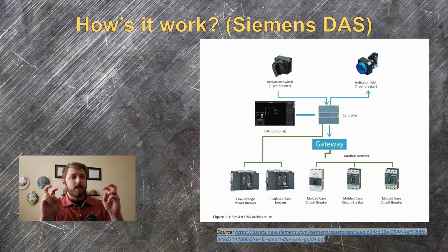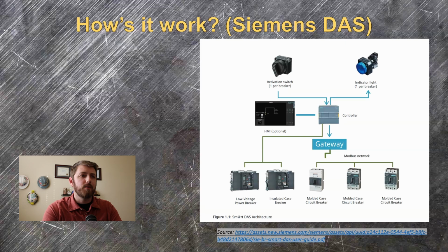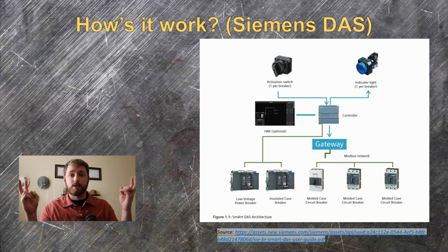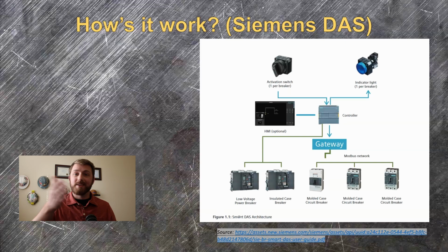Siemens Smart DAS system is similar to Square D's ERMS system. Implementation requires a controller and a communications gateway, and they send the maintenance mode signal to the trip unit over Modbus instead of having a hardwired 24 volt digital input. It just adds complexity. You don't really know why they do that. They get to sell you more stuff, right? No matter what system you're working on, you can usually Google such and such trip unit maintenance mode, and you'll find the document that shows you how to set it up for your system, for your breakers. That's really the foolproof way to do it.